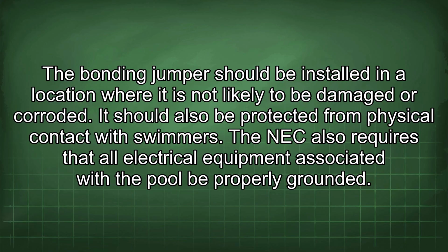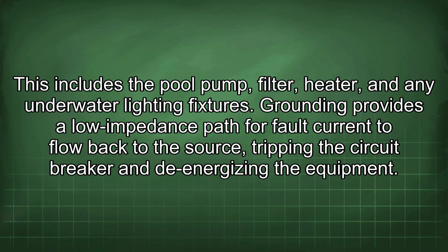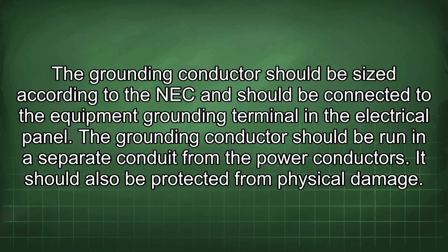The NEC also requires that all electrical equipment associated with the pool be properly grounded. This includes the pool pump, filter, heater, and any underwater lighting fixtures. Grounding provides a low impedance path for fault current to flow back to the source, tripping the circuit breaker and de-energizing the equipment. The grounding conductor should be sized according to the NEC and should be connected to the equipment grounding terminal in the electrical panel. The grounding conductor should be run in a separate conduit from the power conductors. It should also be protected from physical damage.